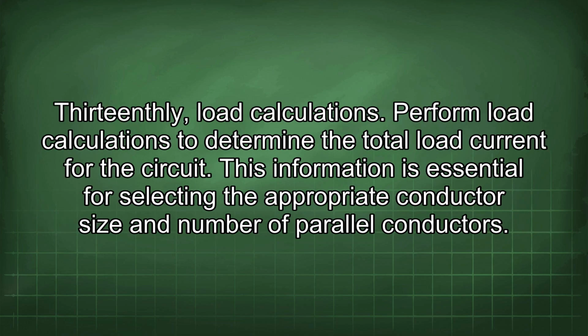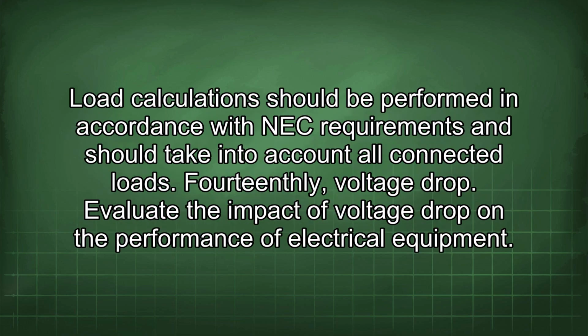Thirteenth, load calculations. Perform load calculations to determine the total load current for the circuit. This information is essential for selecting the appropriate conductor size and number of parallel conductors. Load calculations should be performed in accordance with NEC requirements and should take into account all connected loads. Fourteenth, voltage drop.